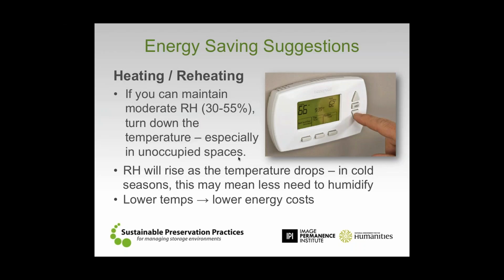But the functional operation of this is that if you live in a cool climate, don't overheat the space, especially if it's not occupied by people regularly. If it's primarily for storage, keep the temperature down. And as long as you can maintain that band of safe relative humidity between 30 and 35% and 55%, then make it as cold as you can go. Oftentimes, as long as you're not moving into a situation where you have to mechanically cool, the goal here is to try and get the space to run passively, to reduce temperature so that you're not heating it mechanically, you're not expending energy there, but also so that you're not introducing mechanical cooling. Let the space go as low as the outdoor environment and the building will let it be.